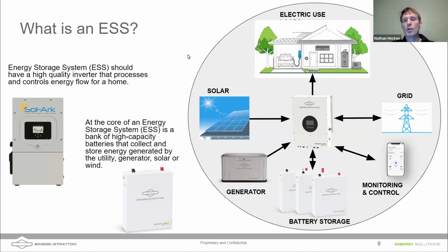And that's becoming more and more important as the majority of customers now have grid-tied systems. Additionally, it's important to have a high-capacity battery bank. That battery bank needs to be able to produce the output power required by the inverter and be able to store enough energy, so a capacity, to deliver a certain amount of time for backup. So we're going to talk about those things.